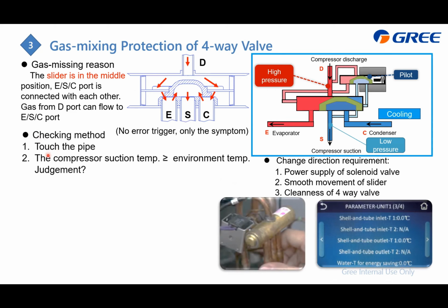And here is the checking method. Of course, you can just touch the pipe like this to feel whether it is hot or cold. If the temperature is close, that means the four-way valve is malfunctioning. And of course you can also double check from the controller. The last one is you can also check the suction side temperature. If it is higher than the outdoor ambient temperature, the judgment is yes, it is confirmed gas mixing, just like this.